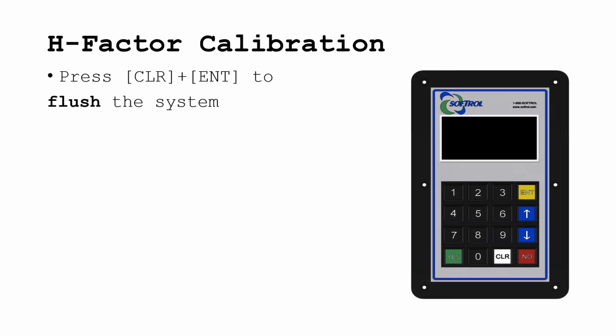Once the calibration is stored, make sure the port valves are open and flush the system thoroughly, using the CLR and ENT keys. And then you are done doing an H-factor calibration for that specific chemical. You should repeat as needed for all other chemicals.